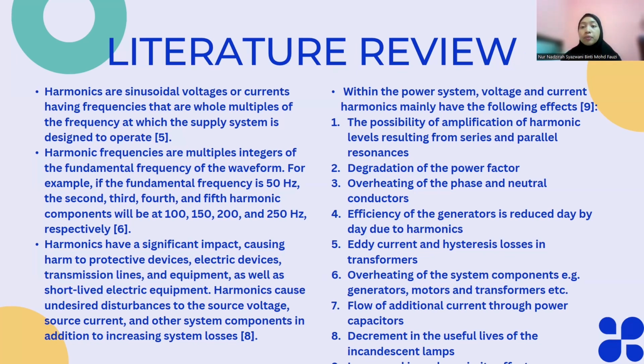Within the power system, voltage and current harmonics mainly have the following effects. First, the possibility of amplification of harmonic levels resulting from series and parallel resonance, degradation of the power factor, overheating of the phase and neutral conductors, and reduced efficiency of the generator day by day due to harmonics. Also eddy current and hysteresis losses in transformers, overheating of system components such as generators, motors, and transformers, flow of additional current through power capacitors, and a decrease in the useful life of induction lamps.